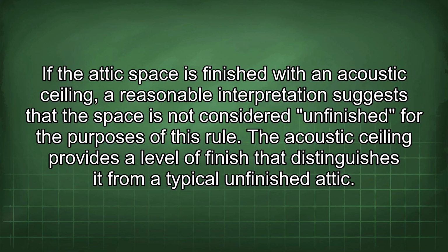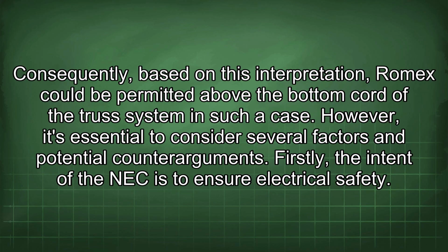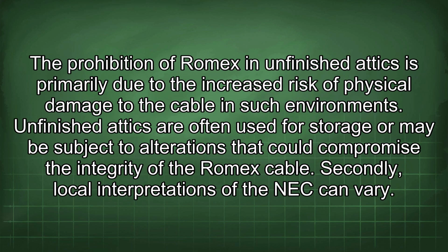The acoustic ceiling provides a level of finish that distinguishes it from a typical unfinished attic. Consequently, based on this interpretation, Romex could be permitted above the bottom chord of the truss system in such a case. However, it's essential to consider several factors and potential counter-arguments. Firstly, the intent of the NEC is to ensure electrical safety. The prohibition of Romex in unfinished attics is primarily due to the increased risk of physical damage to the cable in such environments. Unfinished attics are often used for storage or may be subject to alterations that could compromise the integrity of the Romex cable.